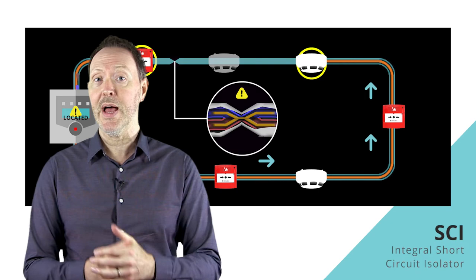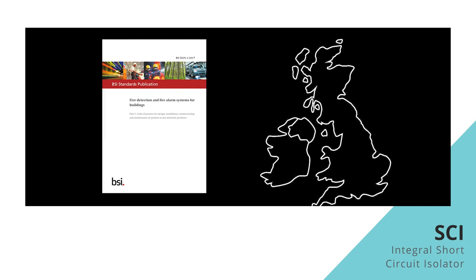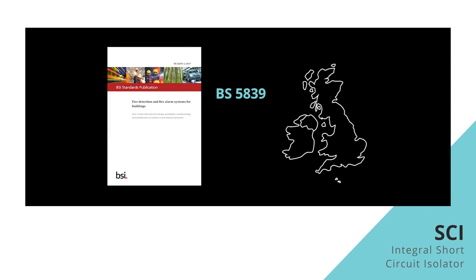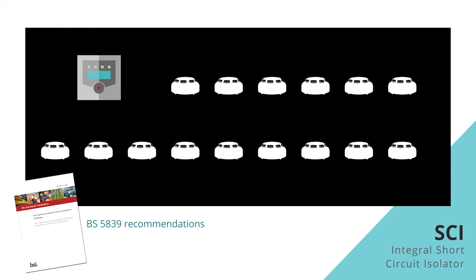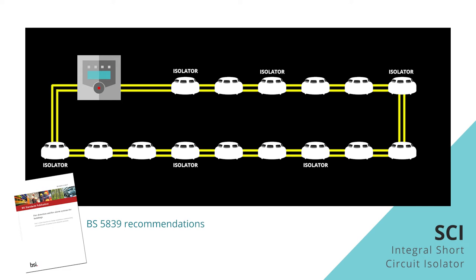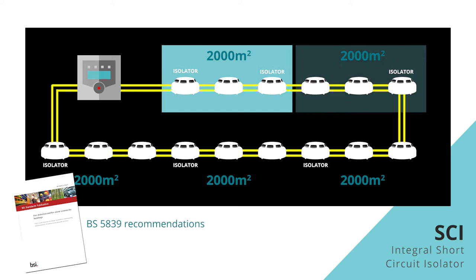Well, it's simply down to the standards for the specific region. Take BS 5839, for instance, for our industry in the UK. It's the go-to guide to design and installation of commercial fire detection systems. In BS 5839, it is recommended that an isolator is only required once in every zone, and that a zone could be anything up to 2,000 square meters. In other words, it's perfectly acceptable to lose a whole zone due to a short circuit on the loop.